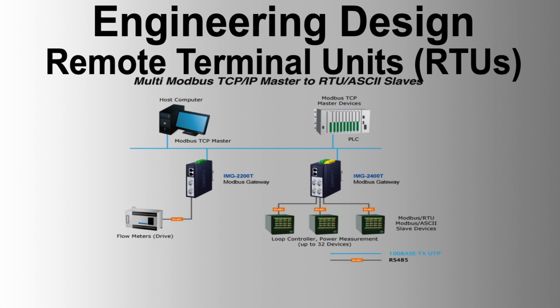Logic capability: RTUs support extensive logic capabilities, including mapping I/O data to a local register array with at least 2048 16-bit registers, a variety of logic input and output conditions, advanced math and logic operations, timer functions, and function blocks for advanced control operations.